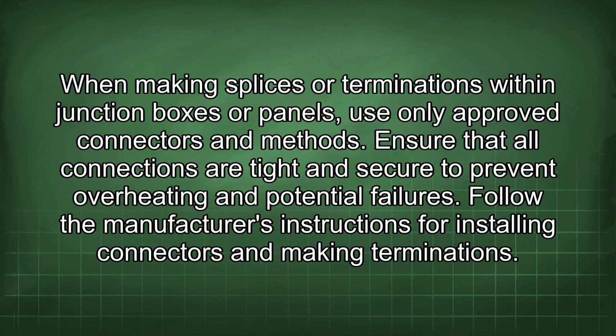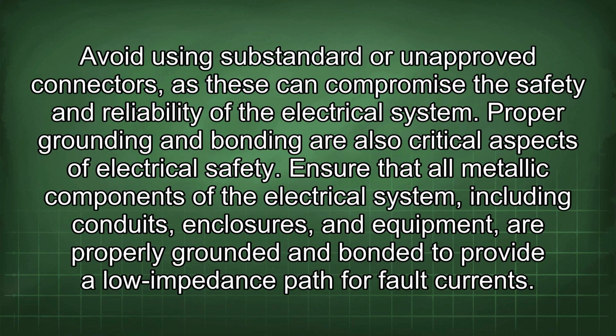When making splices or terminations within junction boxes or panels, use only approved connectors and methods. Ensure that all connections are tight and secure to prevent overheating and potential failures. Follow the manufacturer's instructions for installing connectors and making terminations. Avoid using substandard or unapproved connectors, as these can compromise the safety and reliability of the electrical system.